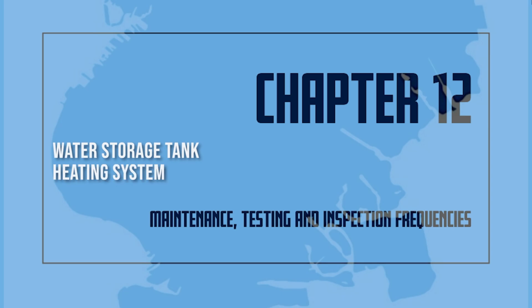Heating system. The heating system and components, including piping without a low temperature alarm, shall be inspected daily. The heating system and components, including piping with a low temperature alarm, shall be inspected weekly. Tank exterior. The exterior of the tank, supporting structure, vents, foundation, and catwalks or ladders, shall be inspected quarterly for damages and weakening. The area surrounding the tank shall be inspected quarterly to ensure it is free of combustible storage, trash, debris, brush, or material that could present a fire exposure hazard, and for any accumulation of material or ice buildup on or near parts that could result in accelerated corrosion or rot.